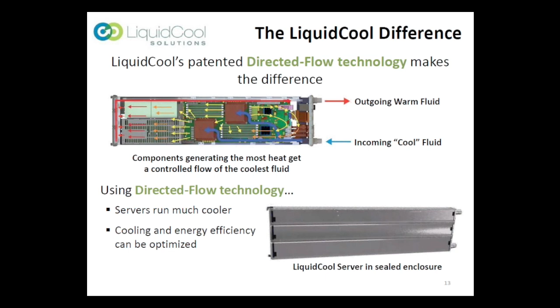So everything gets cooled by the liquid. And then the outgoing warm fluid gets returned to the fluid distribution system, and the warm fluid will get dealt with in one of two ways. Now, what directed flow really enables us to do is keep the components cooler, and we've got control of the flow. The flow, by the way, does not have to be a very high rate. It's typically about a pencil stream of liquid coming out of a faucet. So that's really all the flow we need to provide adequate cooling for a server like this.